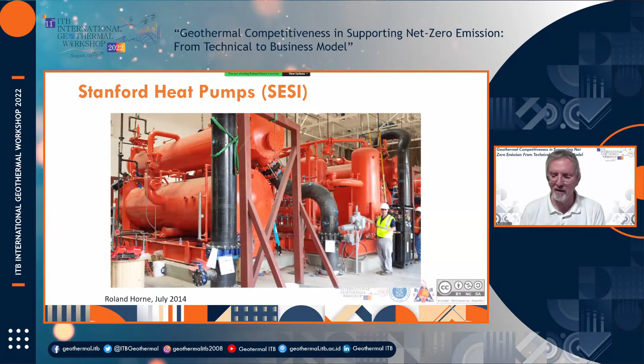This is a system on the Stanford University campus where I work, based upon thermal storage and recycling. There are three giant heat pumps, each about 15 megawatts in capacity, used not in a geothermal sense but for recycling heat on the campus. Over the course of a year we have a cooling load and a heating load, and the chilled water going out to the buildings comes back warmer. Those three large devices exchange the kilojoules from the returning chilled water into the returned hot water and basically reuse them, so over the balance of the year, the heating and cooling loads are more or less the same, the area under these curves.